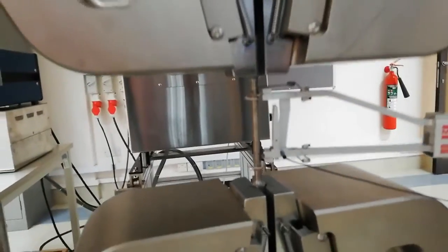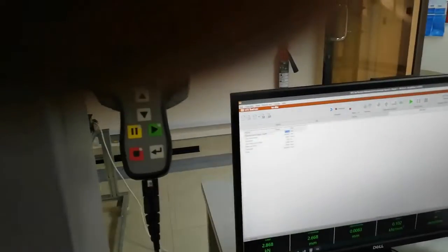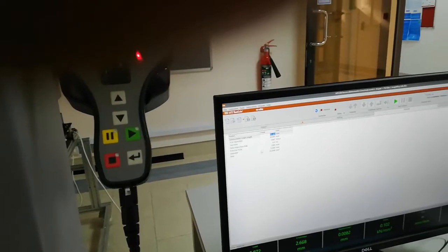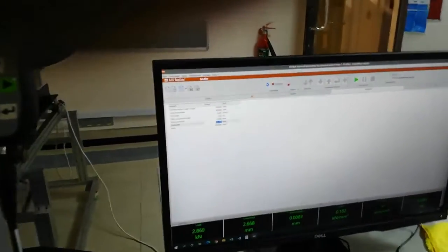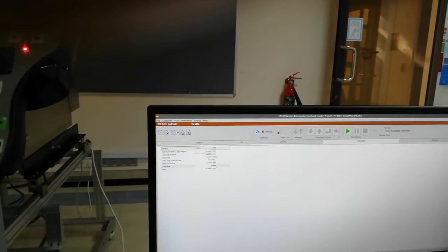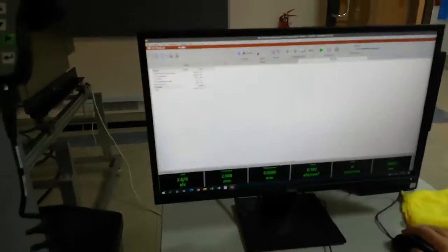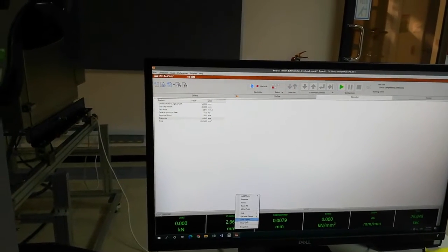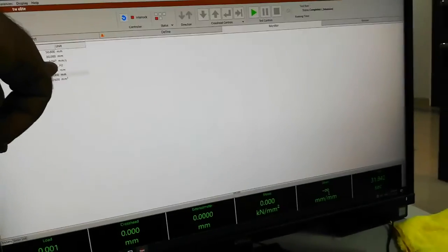Let us set the software. Most values are already set, but we want to change the diameter to 6 millimeters. The area, gauge length, and grip separation are already entered. Before starting the test, we have to zero all signals — the load, the crosshead, and the extensometer. We set zero signal for each of these channels.